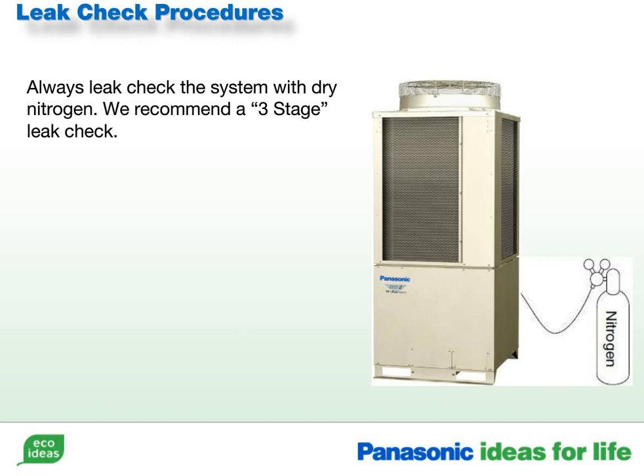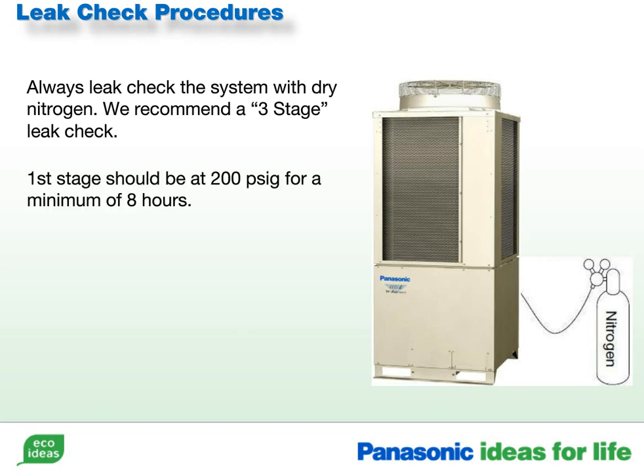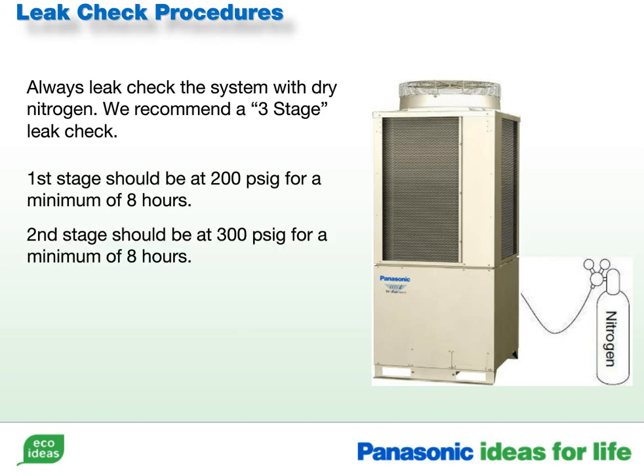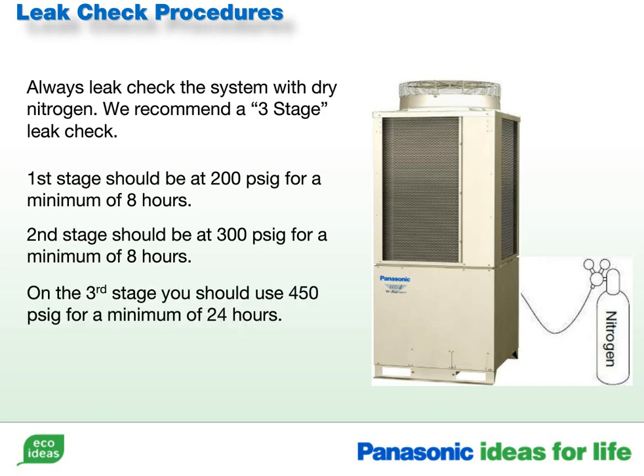Remember to always leak check the system with dry nitrogen. We recommend using the 3-stage leak check method. The first stage should be at 200 psi, for a minimum of 8 hours. The second stage should be at 300 psi, for a minimum of 8 hours. And on the third stage, you should use 450 psi of dry nitrogen, and it should hold for a minimum of 24 hours. This portion of an ECOi installation is the most critical. If you do not perform a thorough leak check at this time, it can become costly and very time-consuming to find a leak later on.